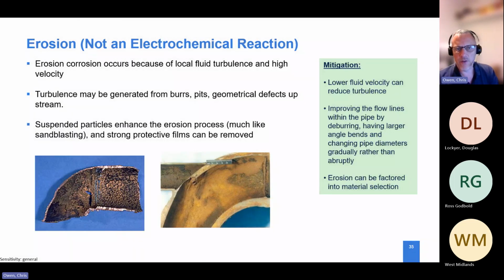Whilst this is not an electrochemical reaction, erosion is something we're starting to see more and more of an issue of. This comes about because if we've got a mixed metal system and corrosion taking place elsewhere as a result of the galvanic series, that corrosion inside the tube can result in debris, which can then go around with the flow of water within that tube.